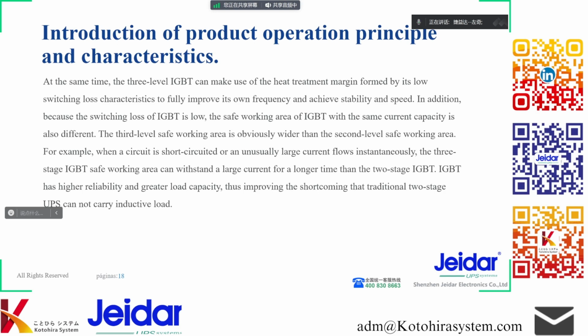For example, when a circuit is short-circuited or an unusually large current flows instantaneously, the three-level IGBT safe working area can withstand a large current for a longer time than the two-level IGBT. The IGBT has higher reliability and greater load capacity, thus improving the shortcoming that the traditional two-level UPS cannot carry inductive load.